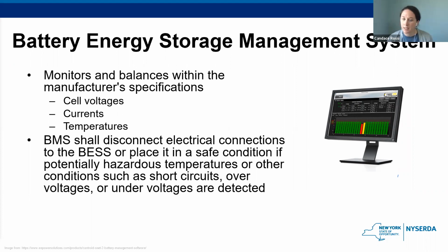So where required by the energy storage system listing, an approved energy storage management system that monitors and balances cell voltages, currents, and temperatures within the manufacturer's specifications. The system shall also disconnect electrical connections to the energy storage system or otherwise place it in a safe condition if potentially hazardous temperatures or other conditions such as short circuits or overvoltage were to be detected. So I know we've talked about this a few times, but this is a really important safety feature of an energy storage system because it's really letting you know what's going on at all times.